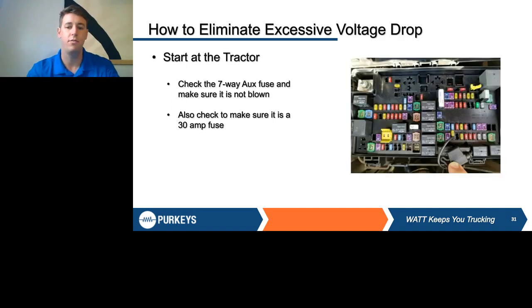Yeah, so when you have this excessive voltage drop, there are a few things that can be causing the problem. So first thing you want to check is the fuses on the truck. Our system, like Jimmy said, is a 20 amp DC-DC converter. It can pull a max of probably 27 amps realistically, but generally 20 to 25 amps. So we want to make sure that that is on a 30 amp circuit. So go to your truck and make sure that the aux fuse is not blown, and if it's not, make sure it is a 30 amp fuse, so that it can handle the power that we're pulling through that circuit.